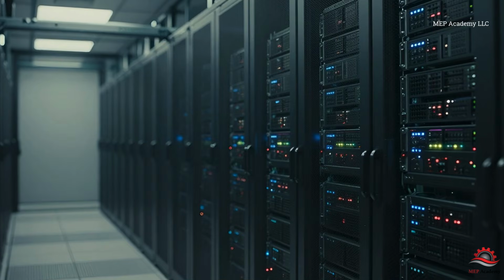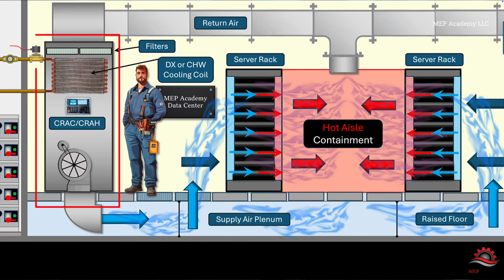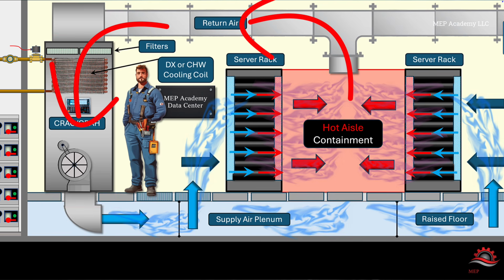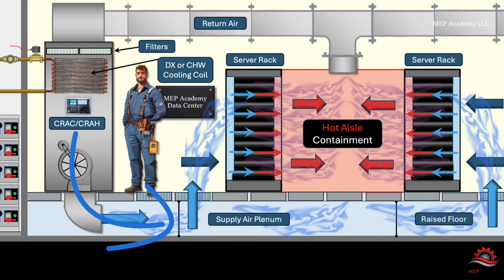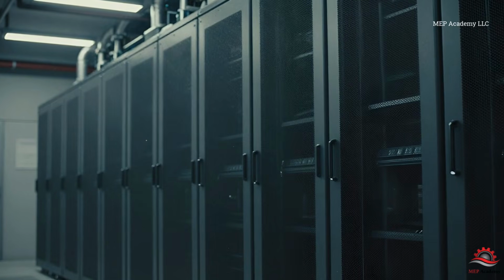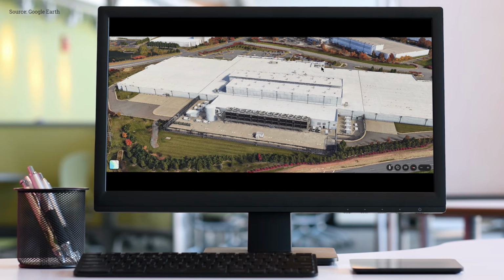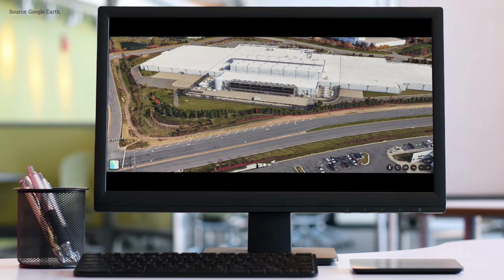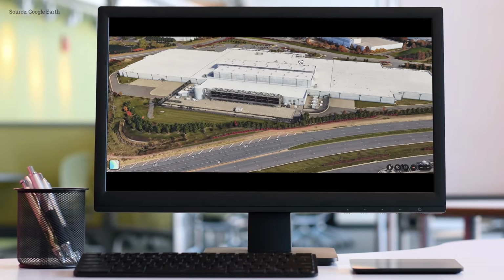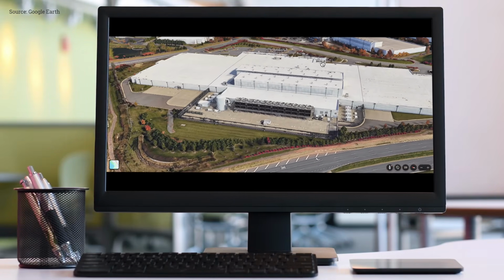Inside the data hall, you'll typically see CRAH units, computer room air handlers. These contain chilled water coils. Hot return air from the servers passes over these coils. Heat transfers into the water, and cooled air is supplied back into the cold aisle. This ties directly into what we covered in the hot aisle versus cold aisle containment video. If the system is water-cooled, it uses cooling towers. Cooling towers reject heat from the system by evaporating water, which is one of the most efficient ways to remove heat at large scale. These are typically located on the roof or outside the building.